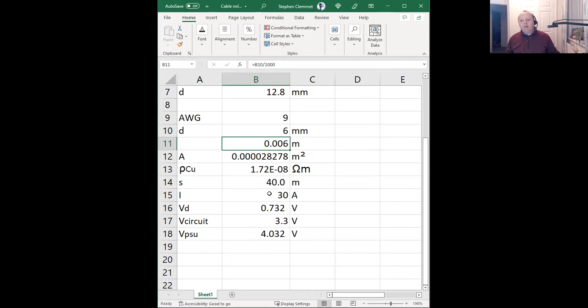So if we was to double that to say 6 millimeter diameter cable, suddenly the voltage drop is going to start to drop across the long cable. Intuitively that makes a world of sense. But there's the proof - if you've got a long cable, how do you deal with it?